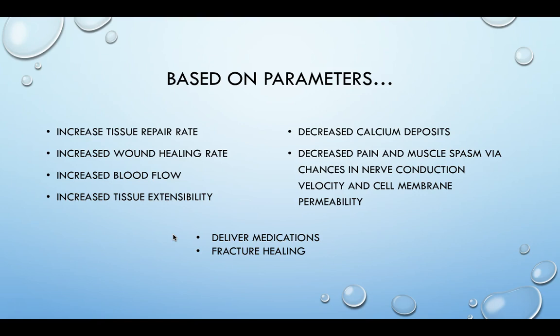Some specialty areas include delivering medications — that's what we call phonophoresis. We've had iontophoresis for e-stim; with phonophoresis we use sound waves to drive medications. There's also potential fracture healing, but those settings are different than those on our typical therapeutic ultrasound machines — you'd need a special generator for fracture healing settings.